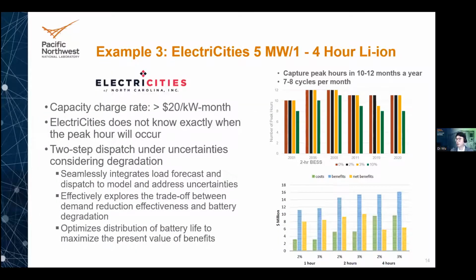In a recent project working with Electricities, we evaluated a 5 to 10 megawatt, 1 to 4 hour lithium-ion battery for capacity charge reduction. Currently, Electricities' member utilities purchase power from Duke Energy Progress under a long-term purchase agreement, and they need to pay the capacity charge based on their coincident demand during Duke Energy Progress system peak hours. With a rate of more than $20 per kilowatt per month, investing in energy storage for capacity charge reduction is a pretty easy business case to make.